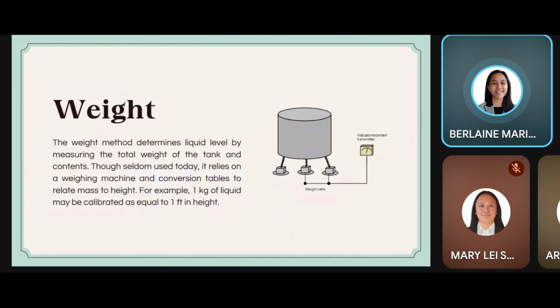Next po ay ang weight, kung saan it is based on the simple relationship between weight and height. The idea is that the total weight of the tank and its contents can be directly related to the liquid level, as long as the density of the liquid stays constant. By using a weighing device, the system calculates the total weight and then converts it into height using calibration tables. For example, the calibration might say that 1 kilogram of liquid is equal to 1 foot in height. However, this method has limitations if the liquid density changes due to temperature or concentration differences.